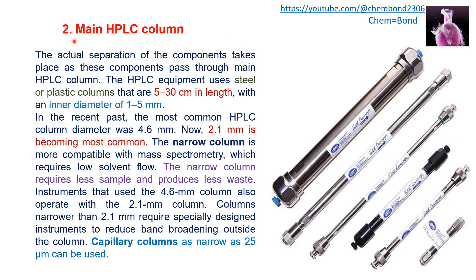The second type is the analytical column, or main HPLC column, where the actual separation of components takes place as they pass through it along with the mobile phase. HPLC equipment uses stainless steel or plastic columns that are 5 to 30 cm in length with an inner diameter of 1 to 5 mm. In recent years, the most common HPLC column diameter was 4.6 mm, but 2.1 mm is now becoming the most common. Narrow columns are more compatible with mass spectrometry, require less solvent flow, less sample, and produce less waste.